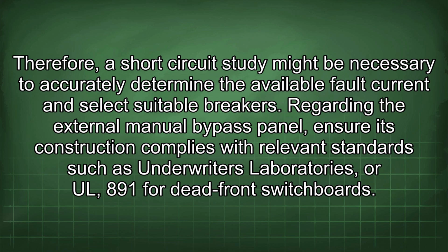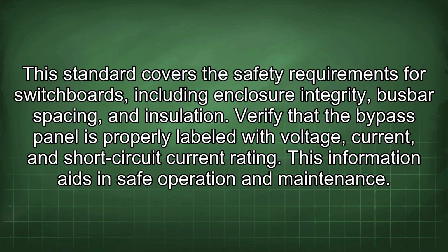Regarding the external manual bypass panel, ensure its construction complies with relevant standards such as Underwriters Laboratories, or UL 891, for dead front switchboards. This standard covers the safety requirements for switchboards, including enclosure integrity, busbar spacing, and insulation. Verify that the bypass panel is properly labeled with voltage, current, and short circuit current rating. This information aids in safe operation and maintenance.